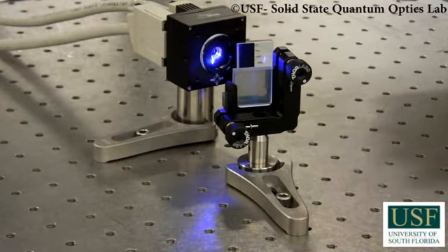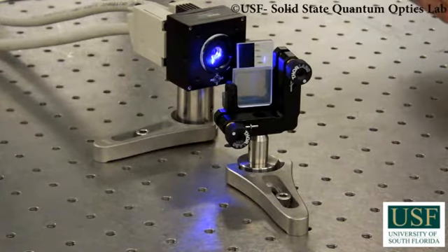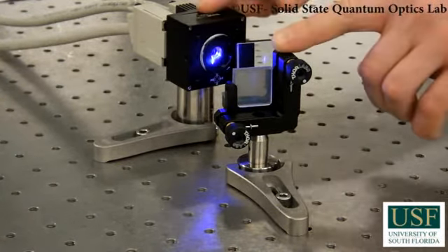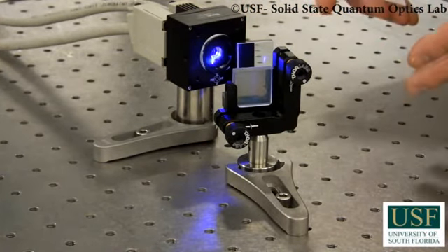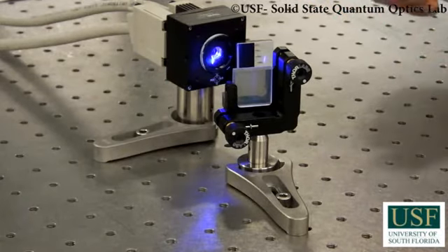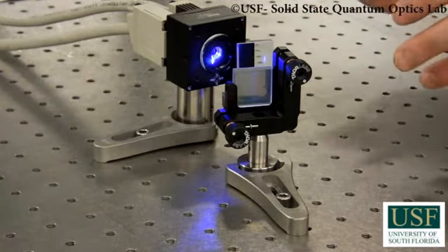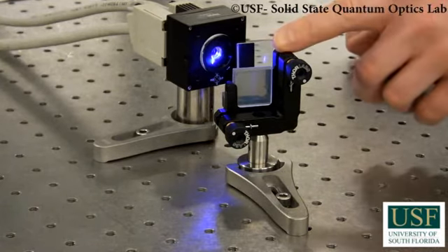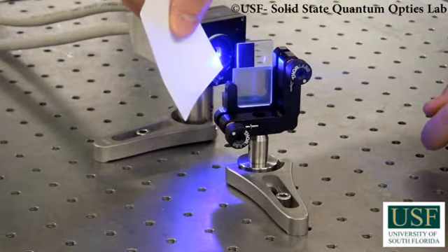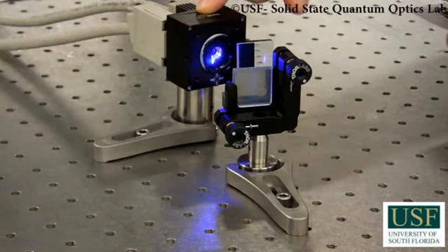This setup is typical of many commercial products or laboratory setups, except for two major differences for demonstration purposes. First, our external cavity is much larger than needed. And secondly, we have mounted it on an optical table out in the open, where a commercial product would be enclosed and stabilized. For this demonstration, I'll be showing you how to adjust the angle of the diffraction grating such that the first order maxima goes directly back into the laser diode.